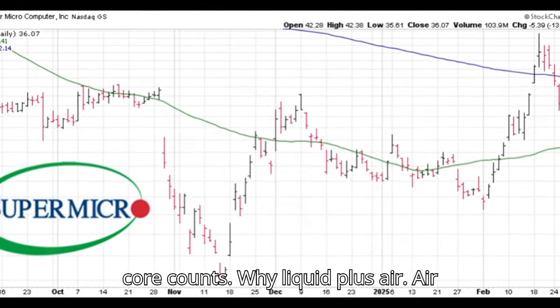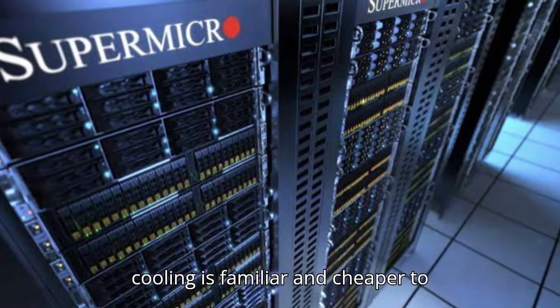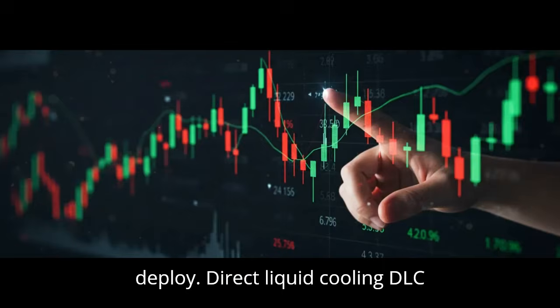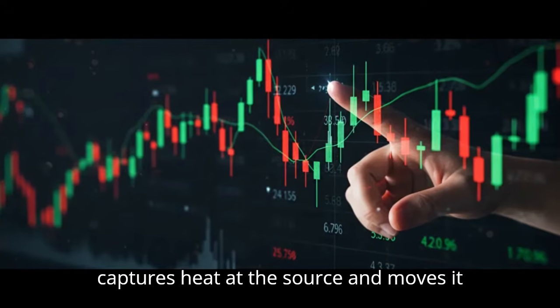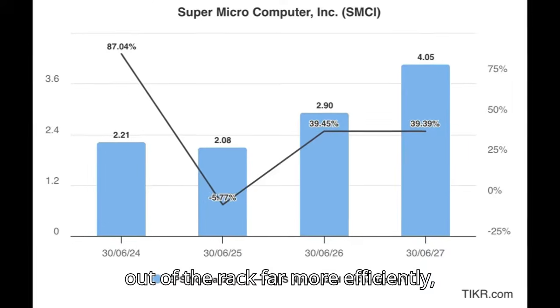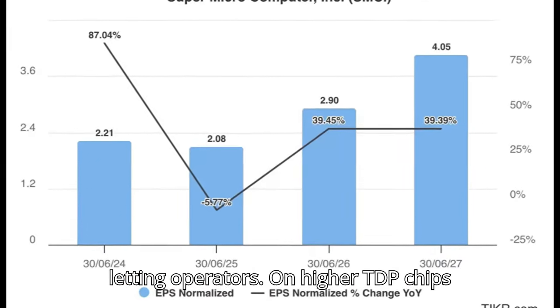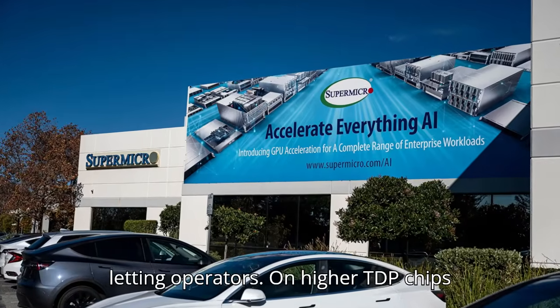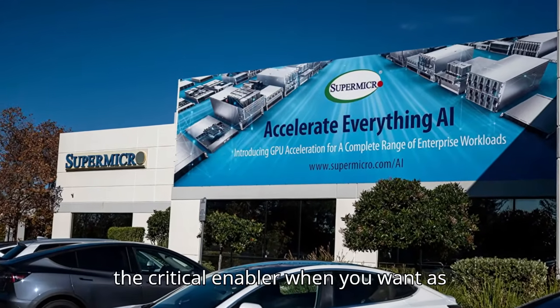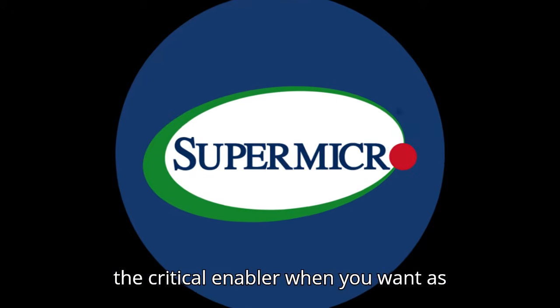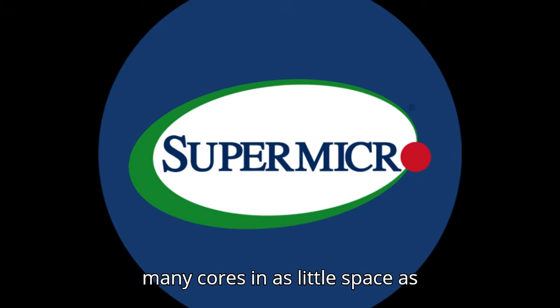Why liquid plus air? Air cooling is familiar and cheaper to deploy. Direct liquid cooling, DLC, captures heat at the source and moves it out of the rack far more efficiently, letting operators run higher TDP chips back-to-back without throttling. That's the critical enabler when you want as many cores in as little space as possible.